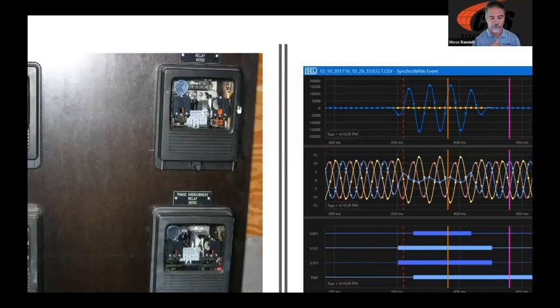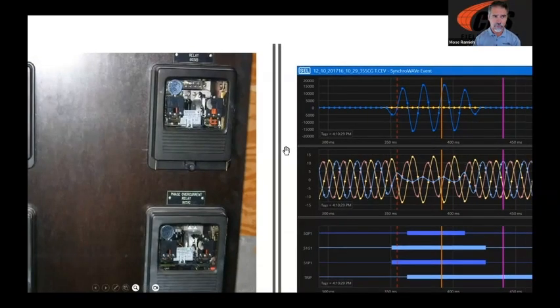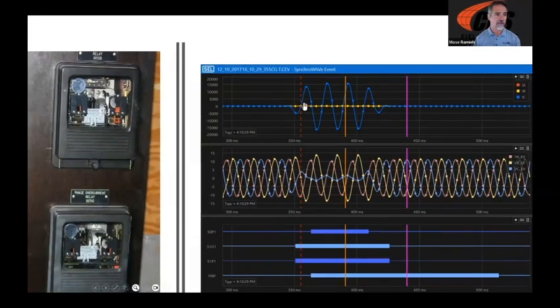Hey, honey, hold my, you know, I'm going to go to the customer site. And once again, they were ready to turn us back on. Now, they did have oscillographic record technology. And I opened that up and I saw a fault that looked very much like this. I'm like, guys, you had a 10,000 amp event. There's something wrong out in your system somewhere. And they're like, no, we rode the system. We didn't find anything. And I said, well, let's go ride it again.